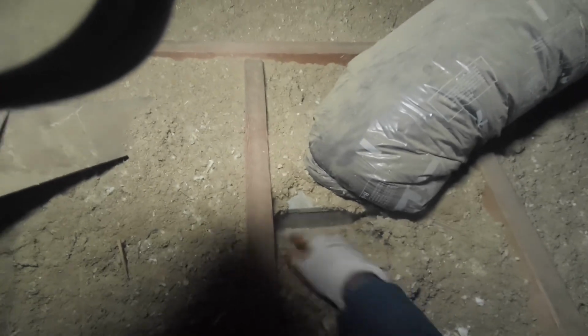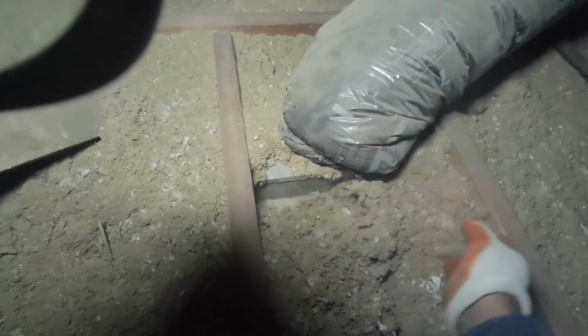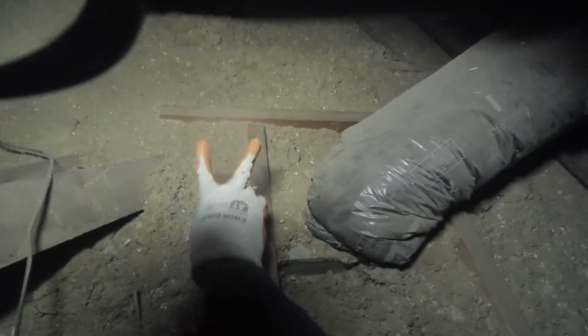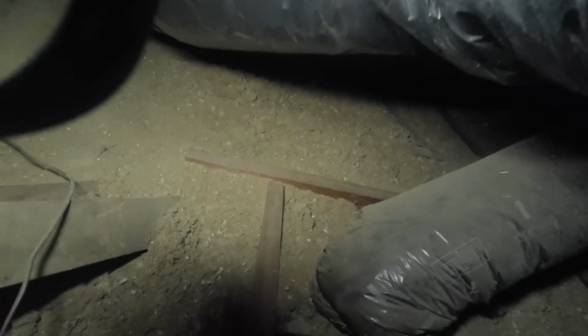This is what SMUD wants, for two reasons. One, this dusty type of insulation can easily get down through here—and I haven't been inside the home, but that manifests as dust around the edge of the vent, not just around the outside edge. They want that sealed up because that dust is known to set off allergies. Reason number two: by sealing it up, your HVAC unit, your heating and cooling bills go down, because you're not wasting temperature into the attic, or introducing attic temperature back into the home during the summertime. So they want it all sealed up. Pretty simple.